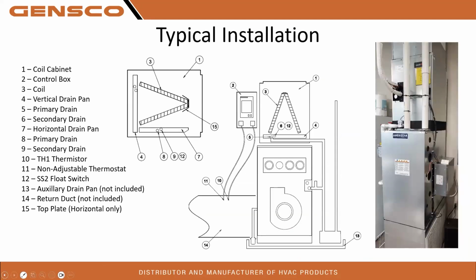All right, so typical installation. You'll see here we have a view of a horizontal and a vertical installation. And this is the furnace we have in our training center of a vertical installation. You can see the coil sitting on top of the furnace there. Again, always make sure your coil's on the supply side of your gas furnace. You do not want it on the return.